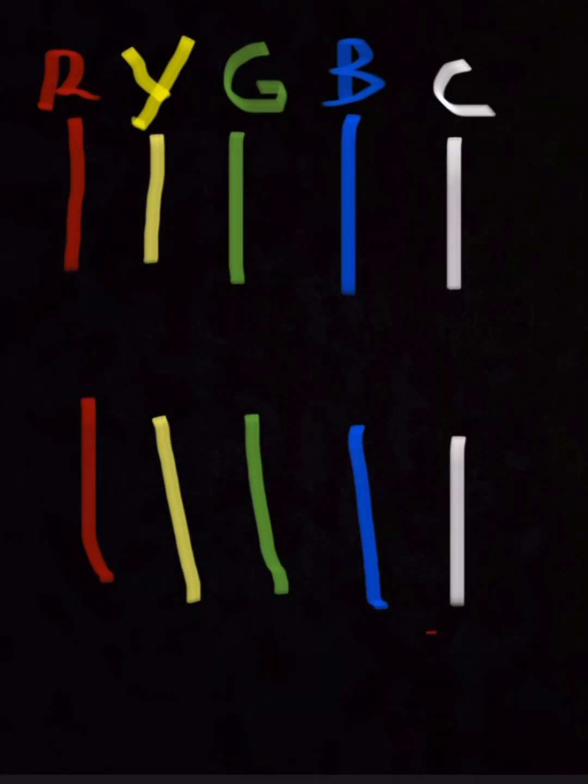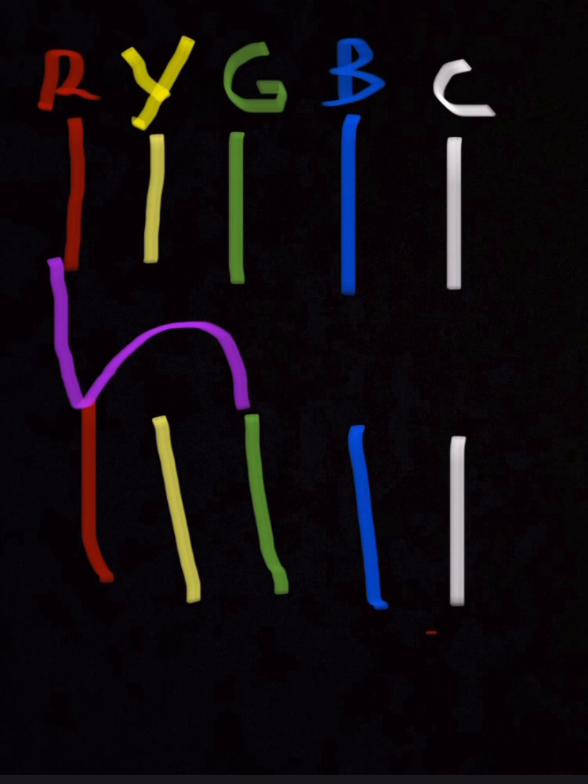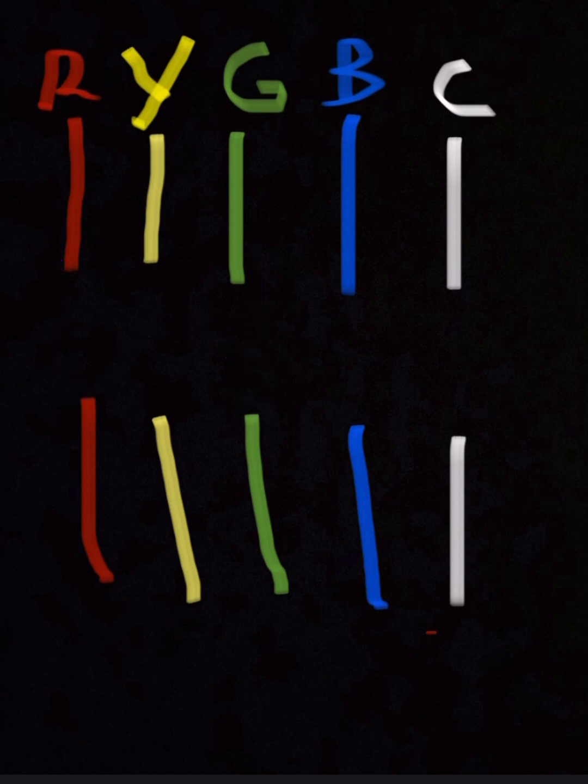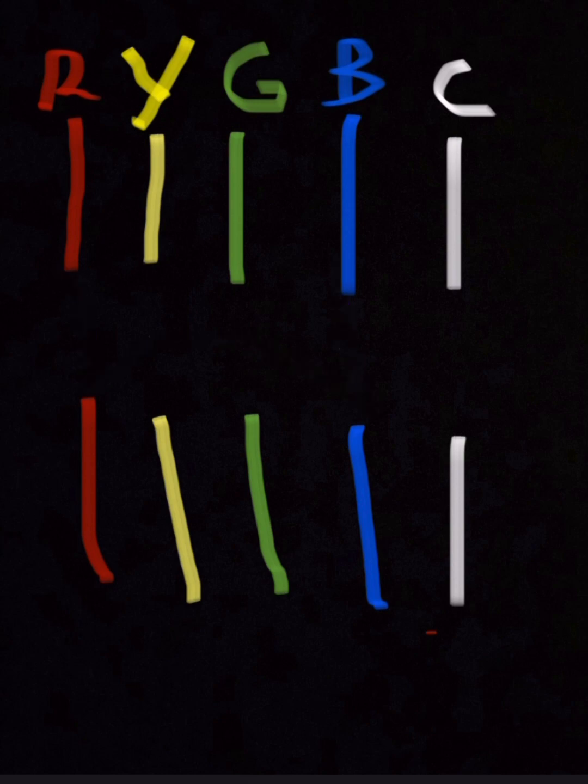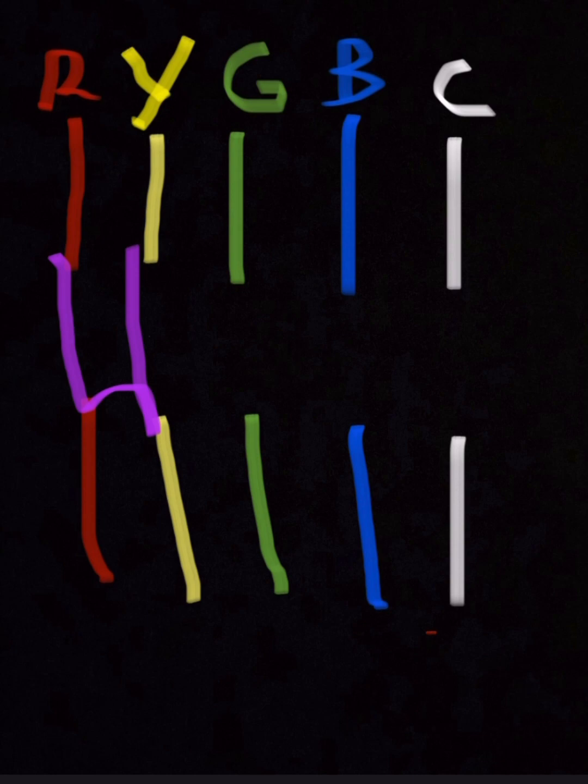Now that you know that your problem is not at the package unit, you want to do the same thing, but you want to involve the thermostat wires. So here I went R to R to G to G, and you want to do that with every single letter. Now you want to do this with the power on with the brand new fuse. If while you're doing this, for example if when we go to the white here, if it pops the fuse right there, boom, you know that's your problem and you need to look into that wire, that color.